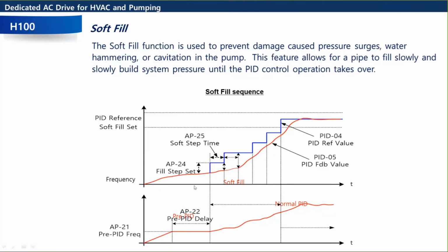So that's what these tables are showing here. There's a pre-PID delay time. It's fully programmable. These AP22, AP24, 25, and these PIDs are all parameters that we're looking at here. So you have a pre-PID delay time, and you could run it at a fixed speed or have it gradually step up. You'll see your frequency creep up until you hit your soft fill level. Once you hit that level, which is typically a pressure point somewhat close to your set point, it's going to automatically flip over to your normal PID operation. So that's what soft fill is.